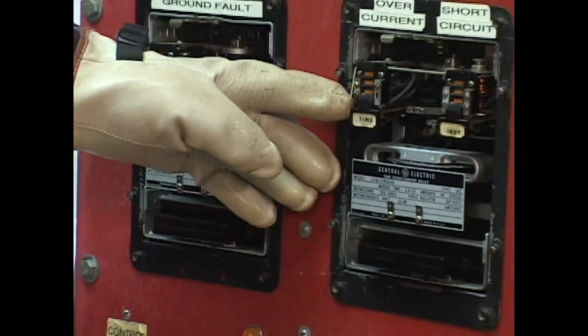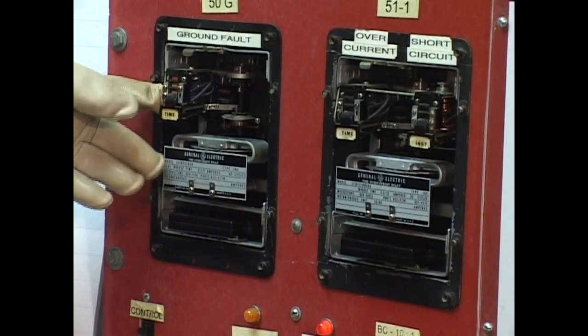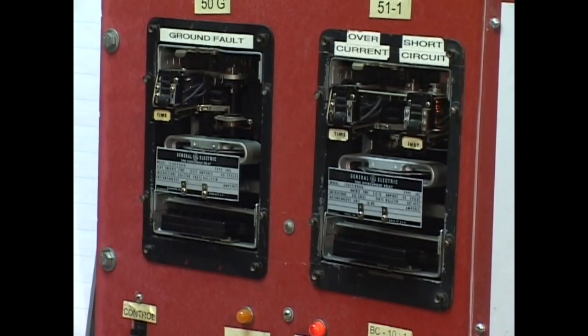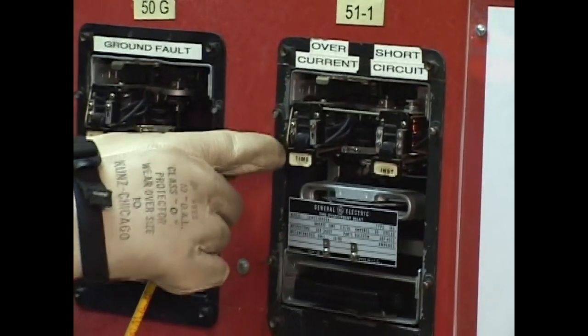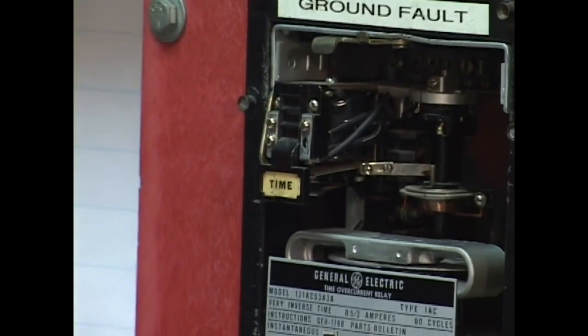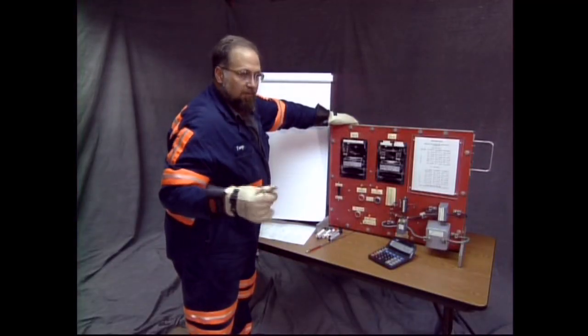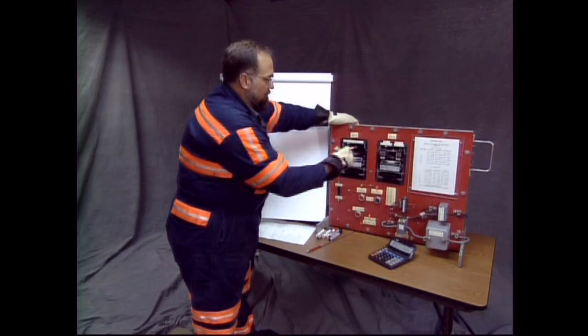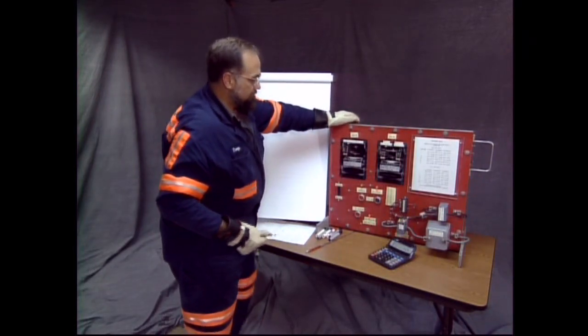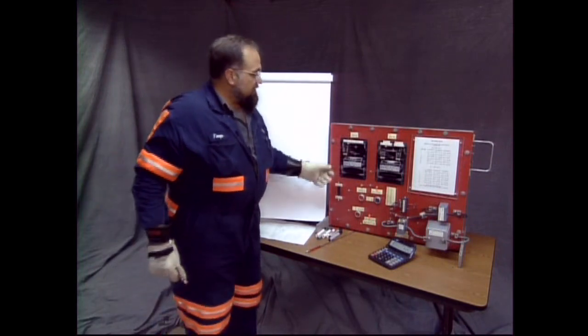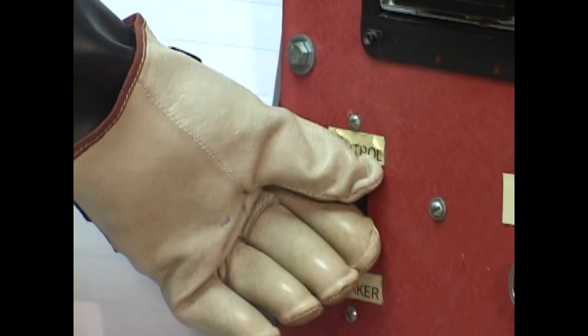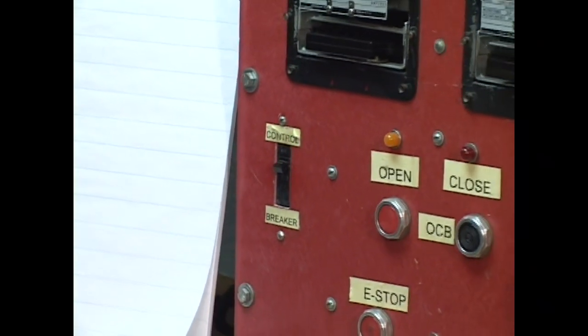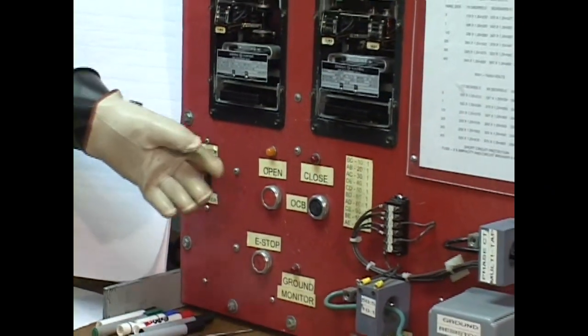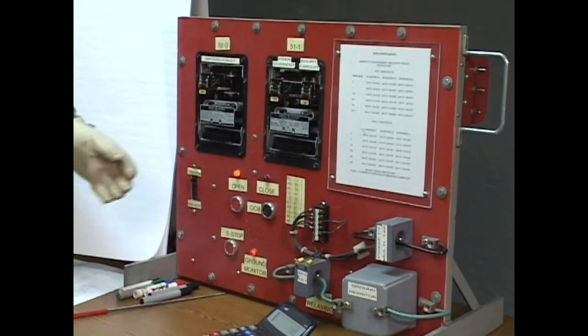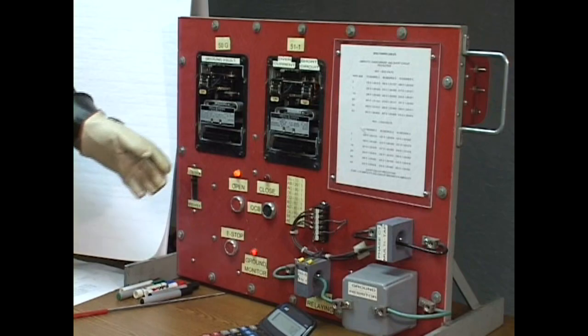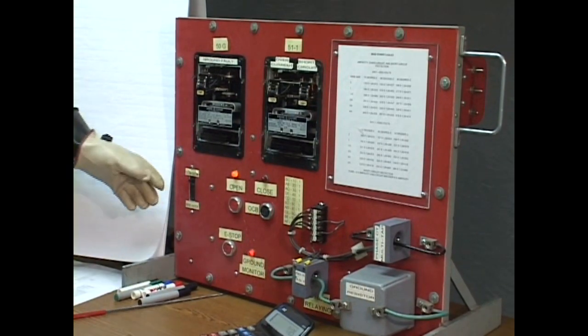You can set these flags back by operating this linkage here, and that closes those flags back off. Now keep in mind, these tap settings here, this part of the relay is live. There is control voltage there, so don't put a pencil or an ink pen with something conductive on it that will ground this device. Okay, now the next statement is I'm going to operate my control breaker to simulate a power outage. My OCB should open and remain open even after power is restored to prove that I have under voltage protection. Okay? And you do that just as I said.